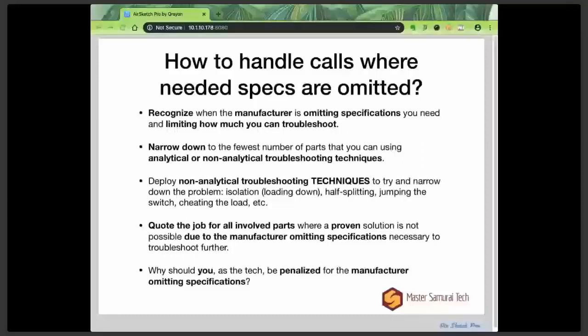If a load isn't working, particularly like AC loads, you'll see this, then you can cheat the load. Use a cheater cord and directly power the load and see if the load will start running. If it does, then you know there's a problem with the supply circuit for that load.